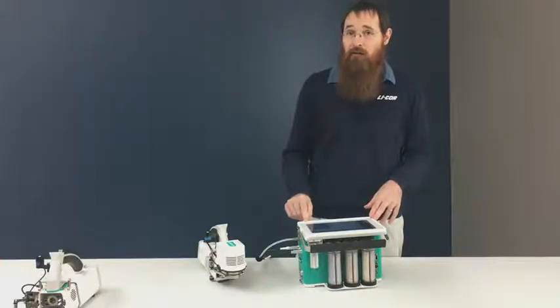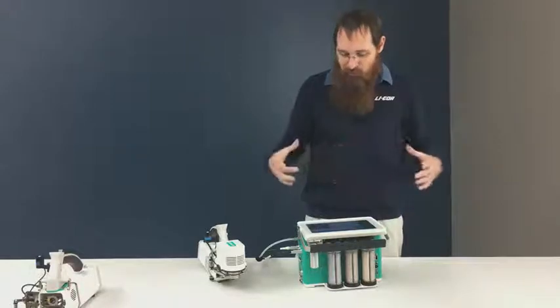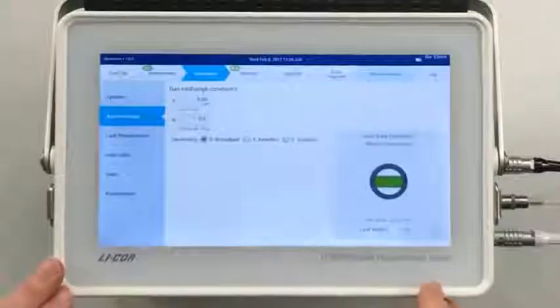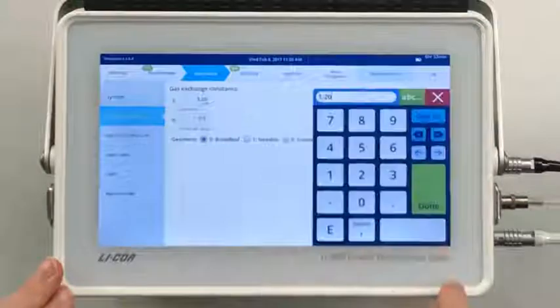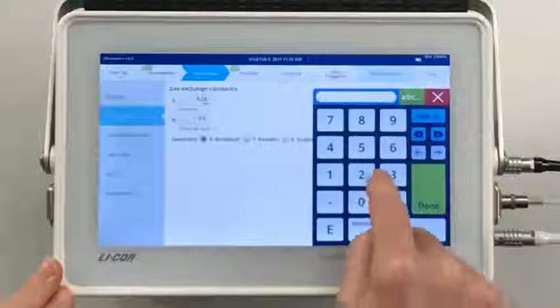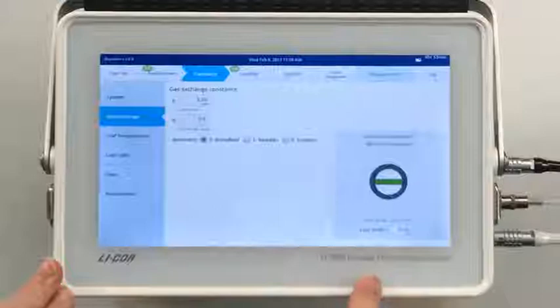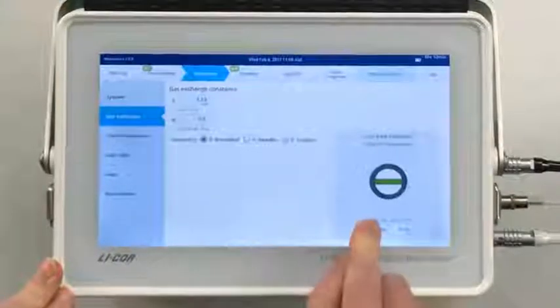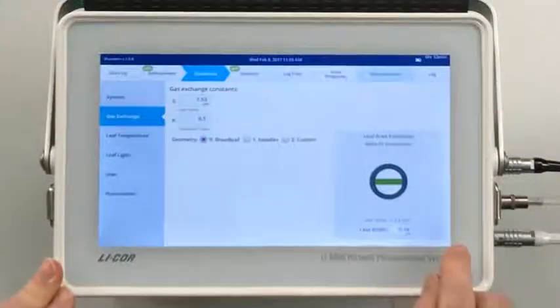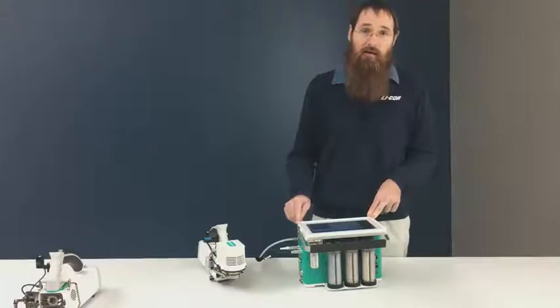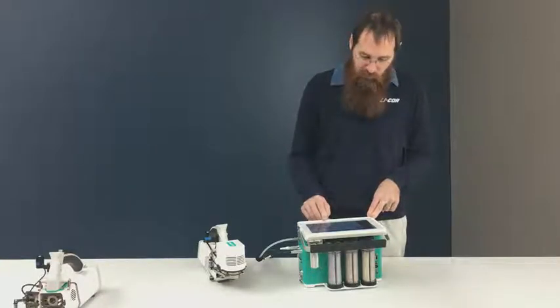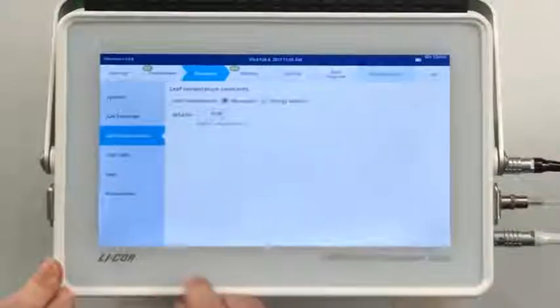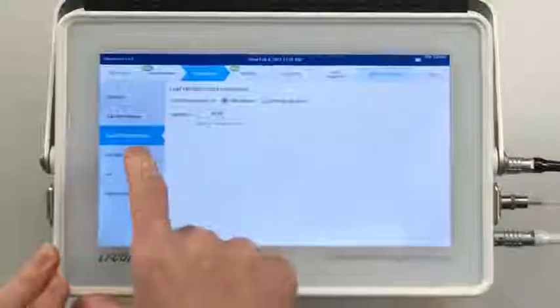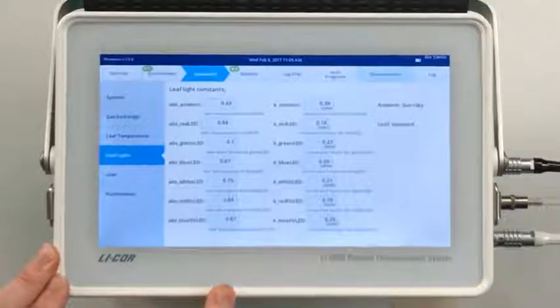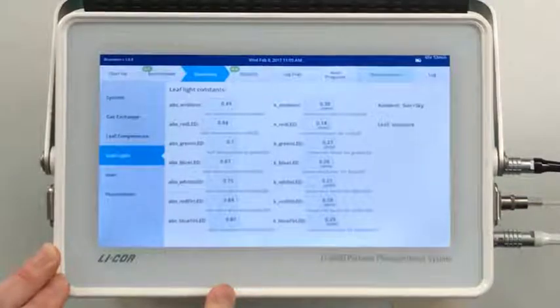If I have linear leaves, something like a grass that's going to cross the chamber, then I can type in a leaf width directly, 0.56. I have a really narrow leaf going across it. And it will compute the leaf area based on the leaf width going through the chamber, and in the case of the fluorometer, it accounts for the curvature of the chamber as it does that. Leaf temperature, this lets me tell it whether it's measured or energy balance. Leaf light, these are weighting factors for light absorption and transmission in the chamber.